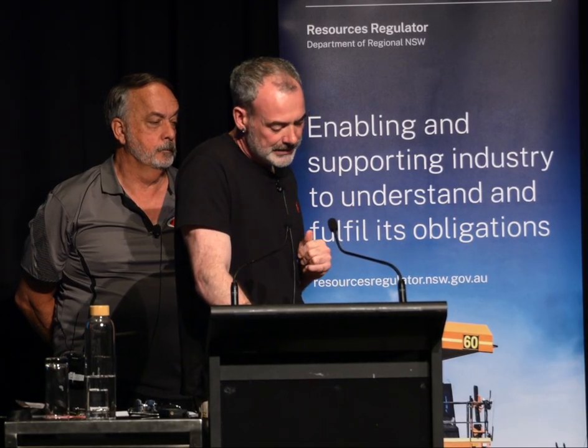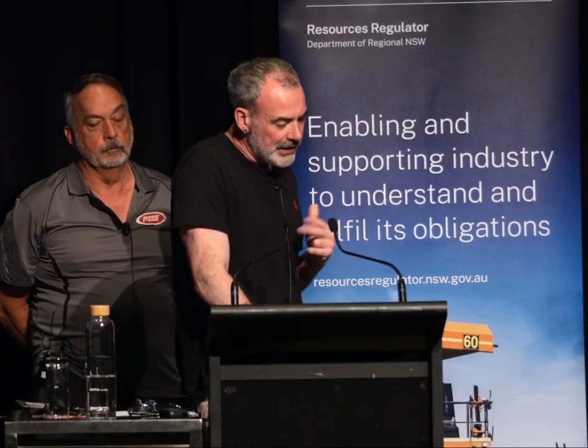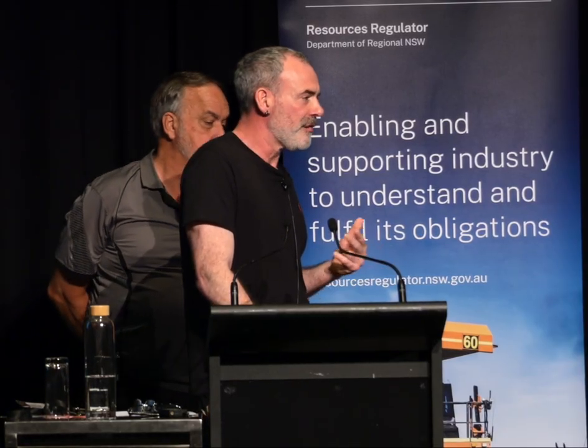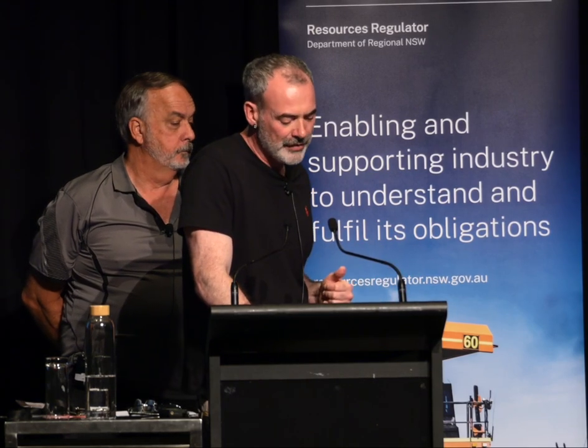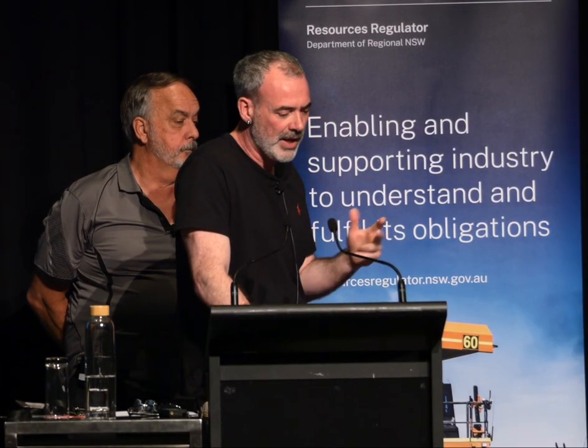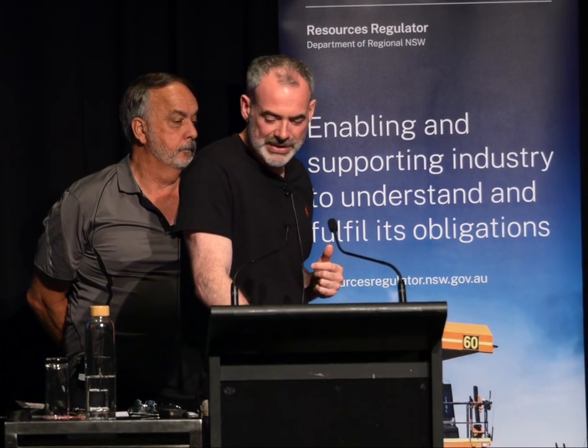So after you do your retrofill, you must verify that the fluid is still K-class, so measure the fire point immediately after the retrofill, and 12 months after. Get your oil testing lab to do a fire point test. They can find somebody that does it for you, and if it's not a K-class fluid, then I guess you need to speak to your service provider and find out why it's not a K-class fluid.